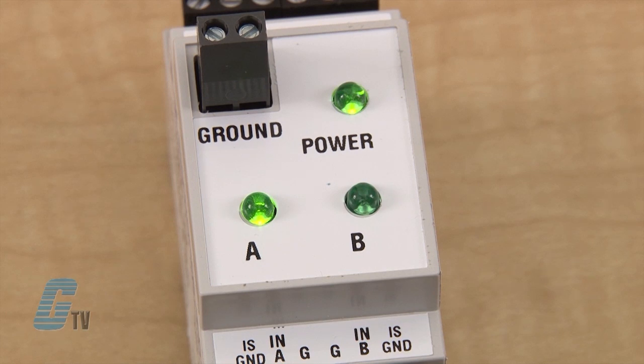When input A is opened, such as with contact opened or high resistance, the dry output contact A opens after 0.5 seconds and the A LED turns off. The B output operates the same way as the A output, but they are independent of each other.